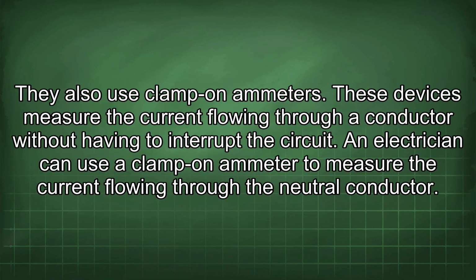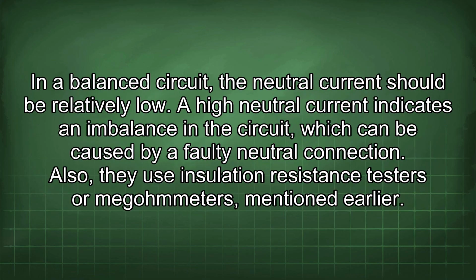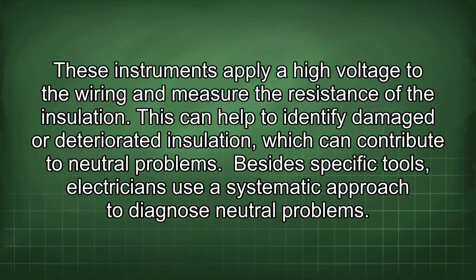They also use clamp-on ammeters. These devices measure the current flowing through a conductor without having to interrupt the circuit. An electrician can use a clamp-on ammeter to measure the current flowing through the neutral conductor. In a balanced circuit, the neutral current should be relatively low. A high neutral current indicates an imbalance in the circuit, which can be caused by a faulty neutral connection. Also, they use insulation resistance testers or megohmmeters, mentioned earlier. These instruments apply a high voltage to the wiring and measure the resistance of the insulation. This can help to identify damaged or deteriorated insulation, which can contribute to neutral problems.